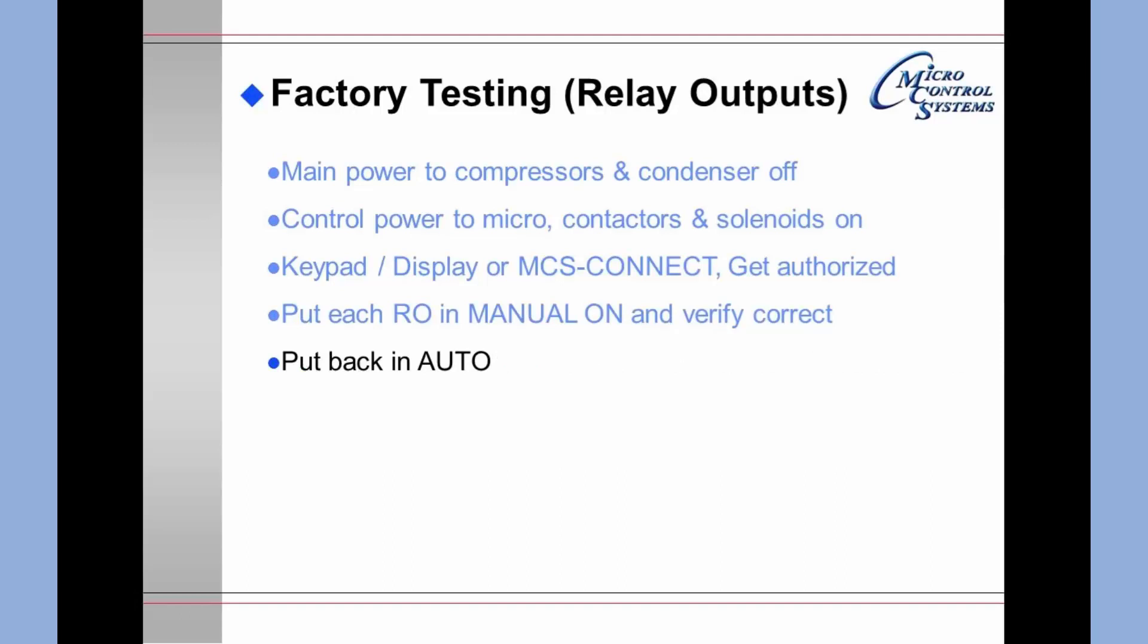Note that when you turn the compressor into manual on, you have to be paying attention to the contactor immediately because it is going to lock out on a safety within a few seconds.